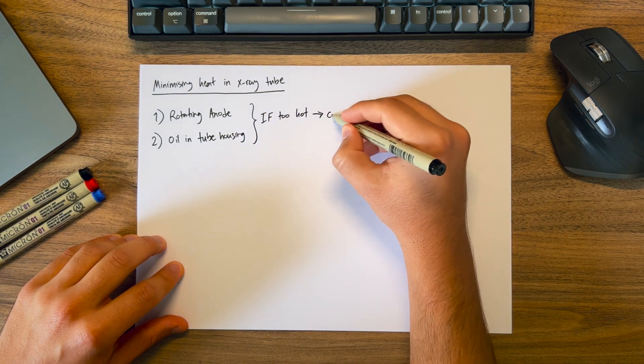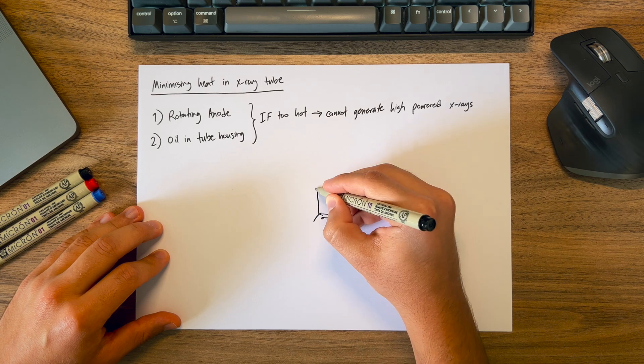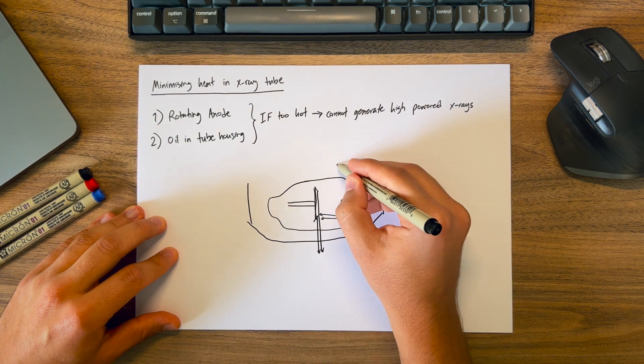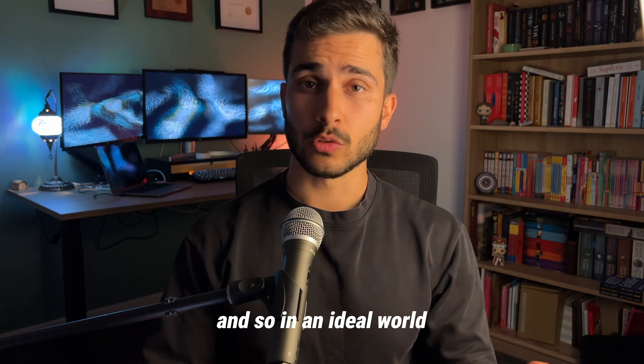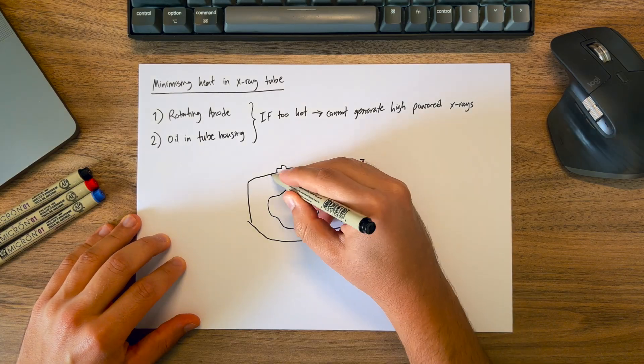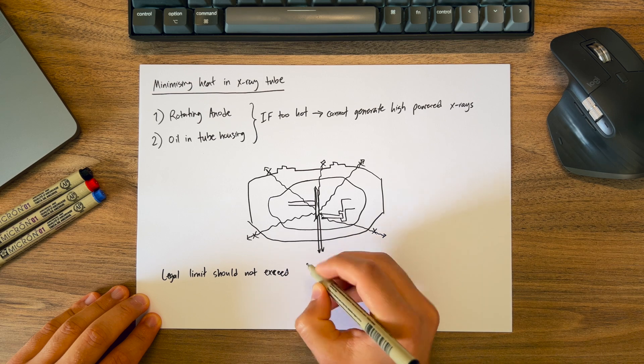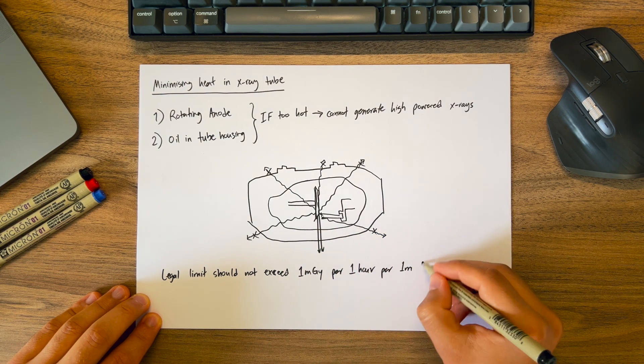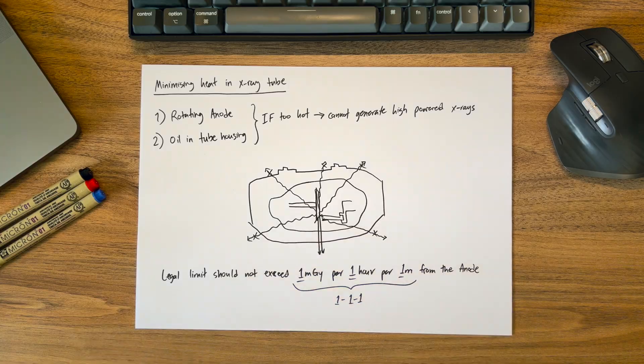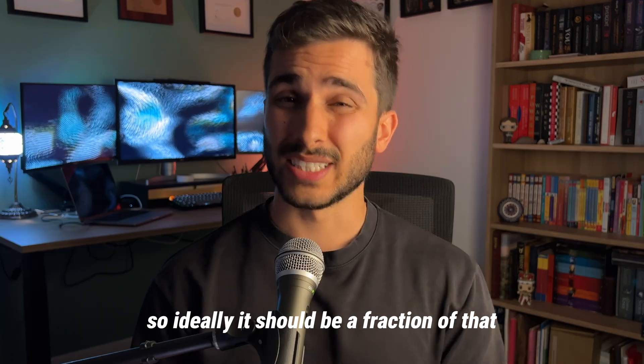If the heat is too high, we can't generate those high powered x-rays that we need to penetrate our patient's tissues. The tube housing has another function, and that is to act as a lead shield, absorbing the x-rays going in all other directions — we're only interested in the x-rays coming out of the exiting window. In an ideal world there are no x-rays leaking from the x-ray tube, but there are going to be x-rays that scatter in other directions, which is what the metal housing is trying to prevent. The legal limit of radiation leakage from an x-ray tube running at its maximum voltage should not exceed 1 mGy per hour at 1 meter from the anode — so 1-1-1: 1 mGy, 1 hour, 1 meter. Ideally it should be a fraction of that.